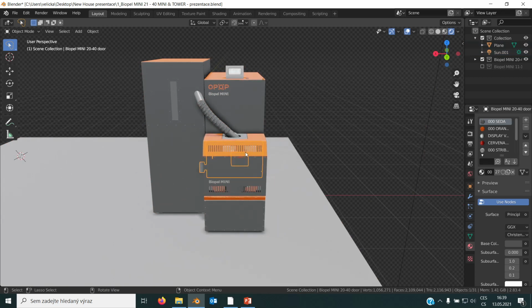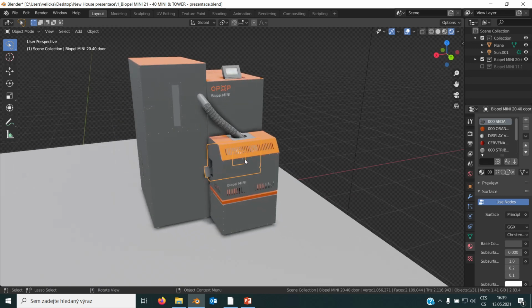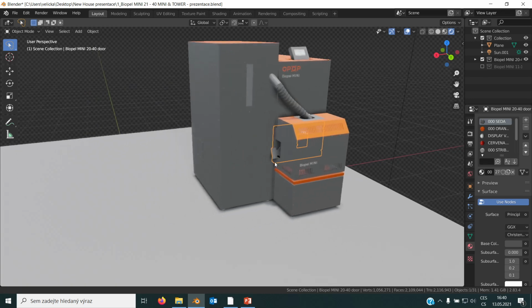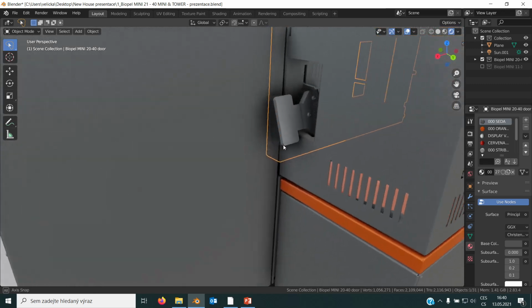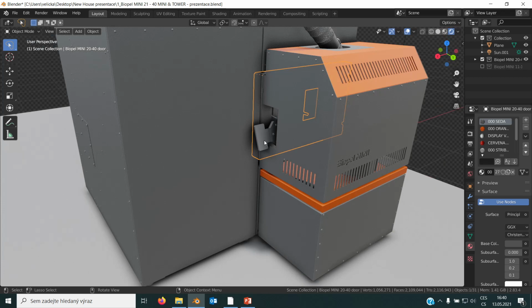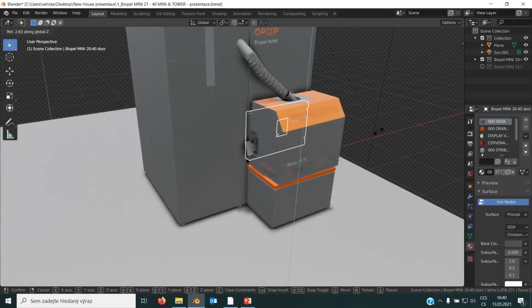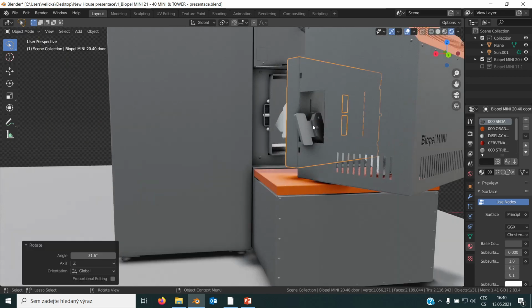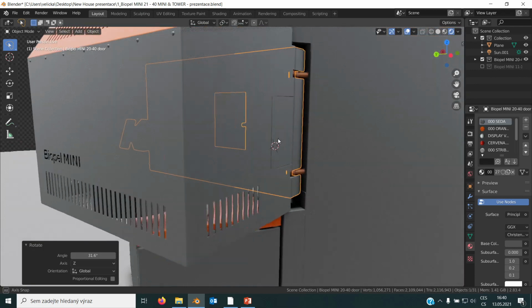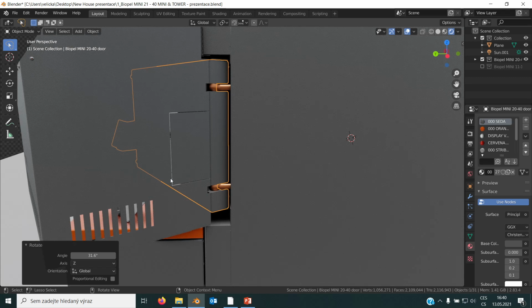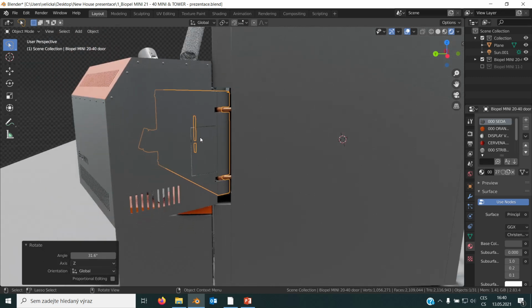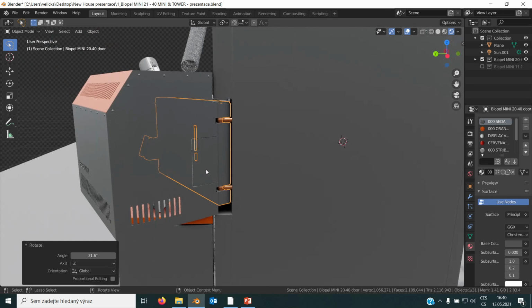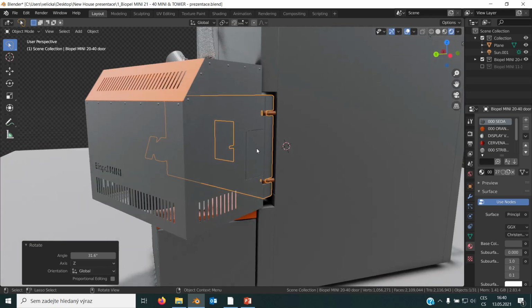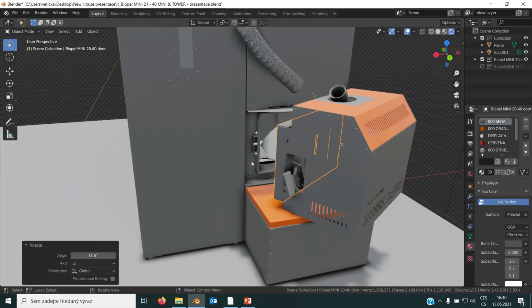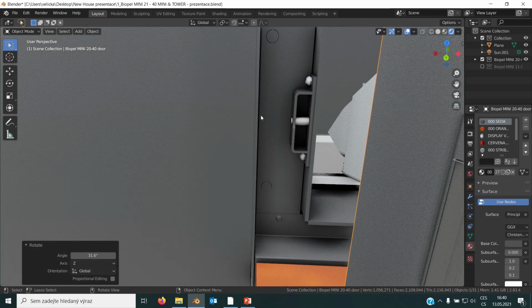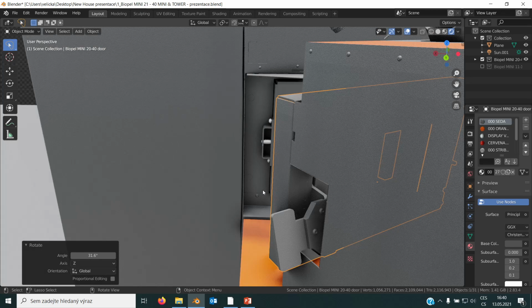If you decide to install the hinges on the left side, you also have to change the position of the closing handle here. The closing handle for the doors is of course on the left side. So when you change the hinges to the left side, you basically remove the closing handle, you open the plate here, you remove this plate from the burner cover, and then you install the handle for the opening on the opposite side. So basically here you have a handle for the door, and here and here you have two hinges, and the doors open to the left side.